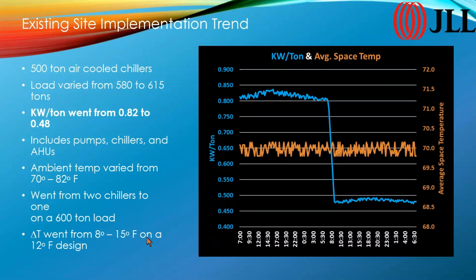And as we changed the delta P set point, the delta T in the system went a little bit broader, a little bit broader, a little bit broader. And then we reached a point where the change in differential pressure set point didn't make any difference at all in delta T. We were down around 5 PSI, and it just didn't make any difference in the delta T. And so there wasn't any point in going any lower. That's the last commissioning step in the load side.